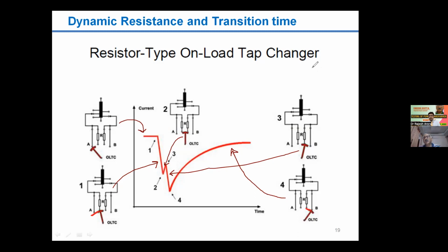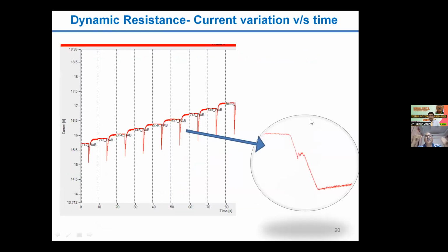And again, when the tap is in position 4, the final position, when the tap change has taken place, the current will increase and will reach near to its original value. So this way the tap changing procedure works, and nowadays the test kits which are coming record these current variations, and on the basis of these current variations, problems or issues in the tap are identified. If there are some issues, those are indicated by this kind of test, shown again by the next curve. As you see, the current variation with respect to time, one of the portions has been enlarged.